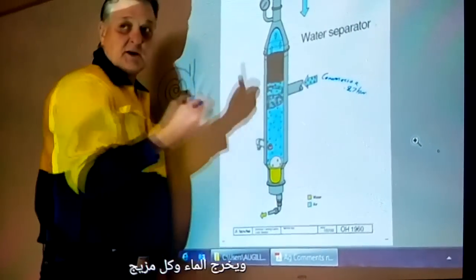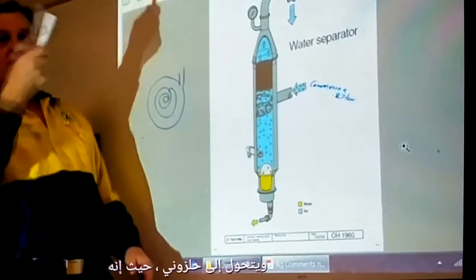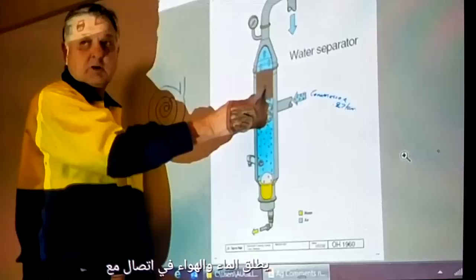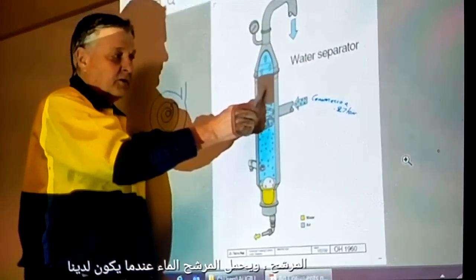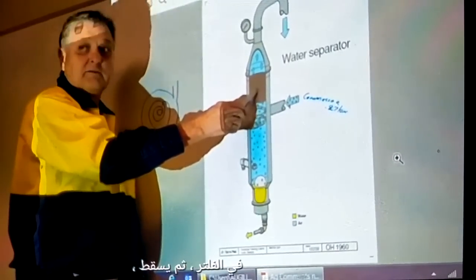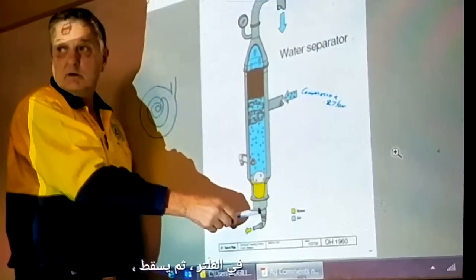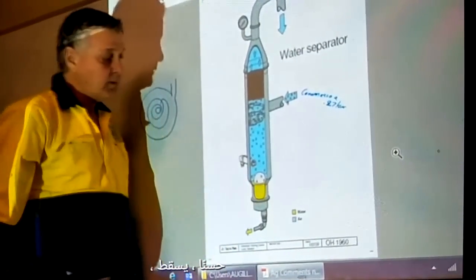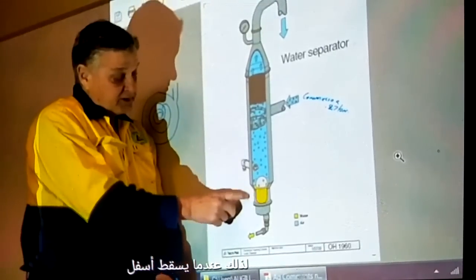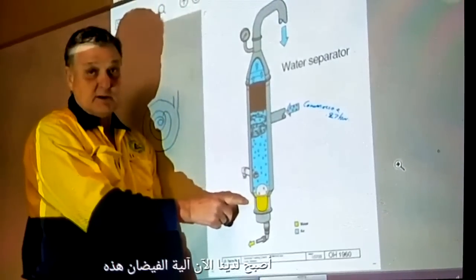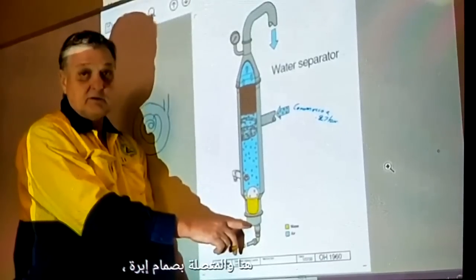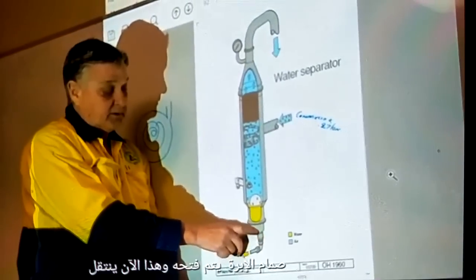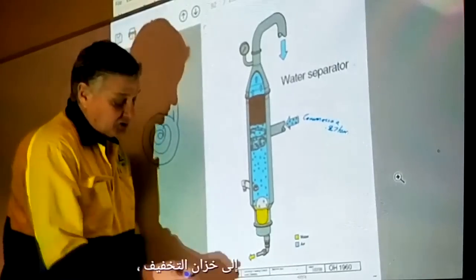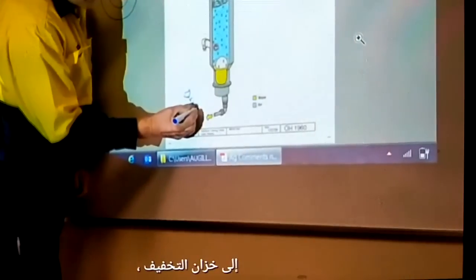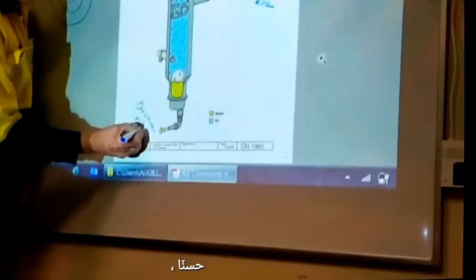So the water just doesn't come in here and go out. The water and air mixture comes together and it spirals. As it's spiraling out, water and air come in contact with the filter. The filter holds the water, and when we have enough water in the filter, it drops down. When it drops down, at the bottom of the separator we have this float mechanism here, which is connected to a needle valve in here. Float comes up, the needle valve opens, and this now goes to the dilution tank. So the water goes to the dilution tank.